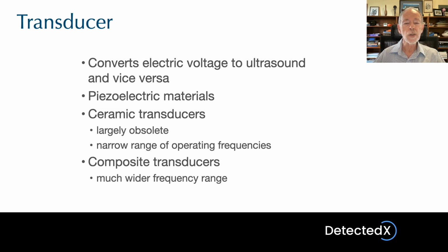This is the component in the probe which creates transmitted ultrasound pulses and receives the returning echoes and converts those into electrical signals. The transducer is made of a piezoelectric material, which means that when pressure is applied to it, it generates a voltage. If that is a time-varying pressure, then there will be a time-varying voltage.